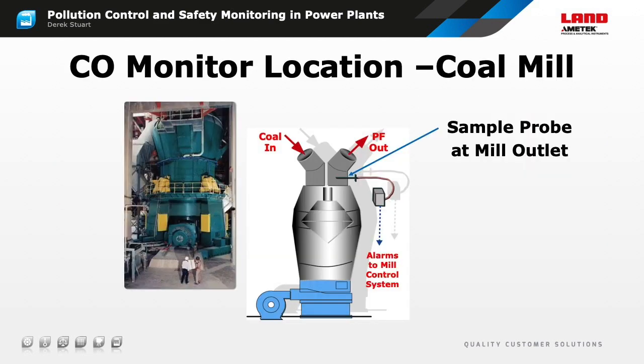The best place to sample the gases within the mill is at the classifier outlet. There's 2 reasons for this. Firstly, the fuel particles are all moving in the same direction, so an insertion probe can be shielded to prevent abrasion. And secondly, the gases have been thoroughly mixed by the movement of the pulverizer, so we can be confident we're measuring a representative sample of what's going on inside it.